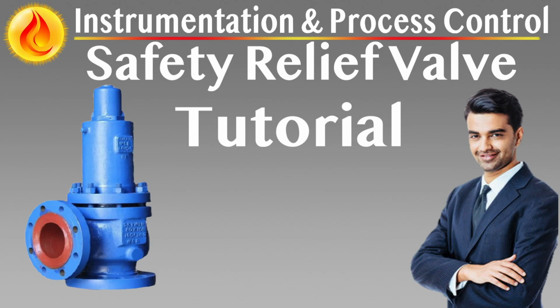Regulatory and operational considerations. In jurisdictions where pressure equipment regulations are strict, careful documentation of allowable overpressure and system dynamics is essential to justify the use of non-balanced valves. Redundant relief valves or differentiated set pressures may be used to ensure that no valve is exposed to adverse back pressure when multiple valves are relieving in parallel.